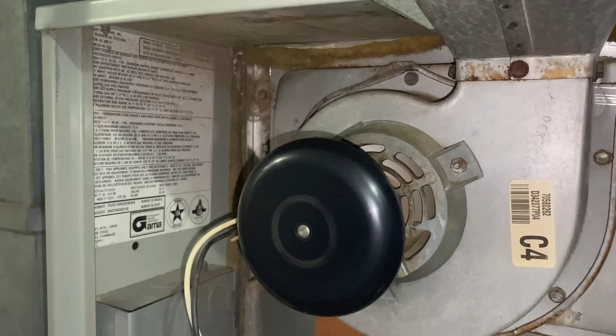Okay. Let's turn this on. And while we were talking about this, we heard this thing come on. So the click is the relay. The relay is telling the inducer assembly to run. And once that pressure switch senses pressure there, the rest of the sequence should start. So we're going to hold this down, and if need be, I'll wrap this with some tape to push it in for testing purposes. But let's see what happens.